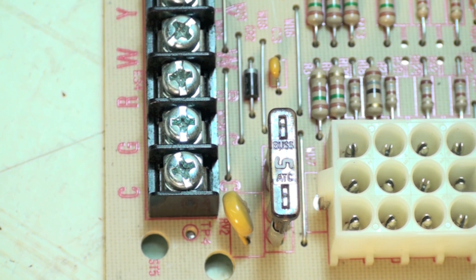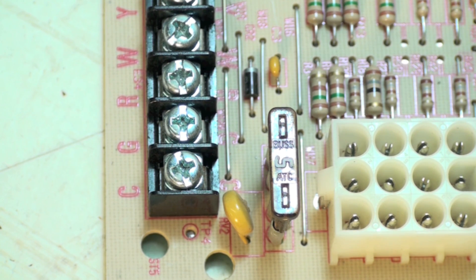That is your low voltage fuse. It blows because there's been a short in the low voltage control somewhere, and that short needs to be found. You'll put another fuse in it, it'll probably blow again.